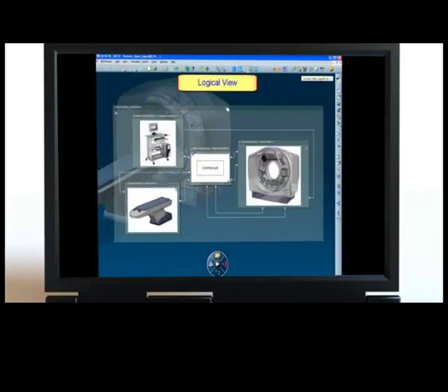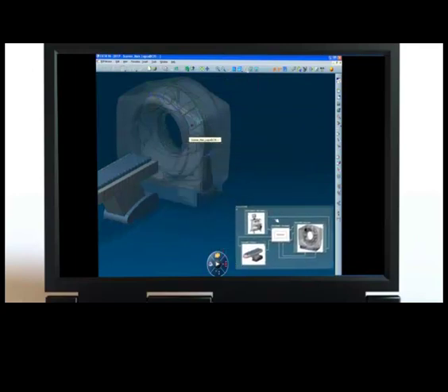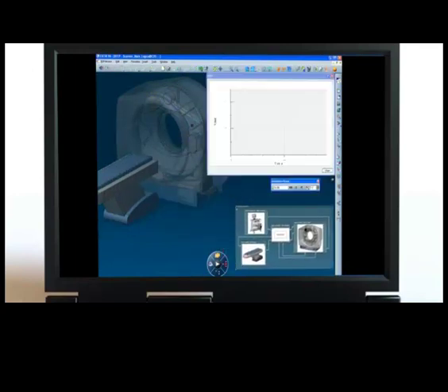The maximum X-ray absorption for an adult is 150 millirems. Looking at the system definition, you can validate that the allowable dosage is outlined within the functional view. Any dosage above 150 millirems will cause the CT scanner to sound an alarm and shut down to ensure patient safety. Real-world behavior is simulated virtually with the entire product definition.